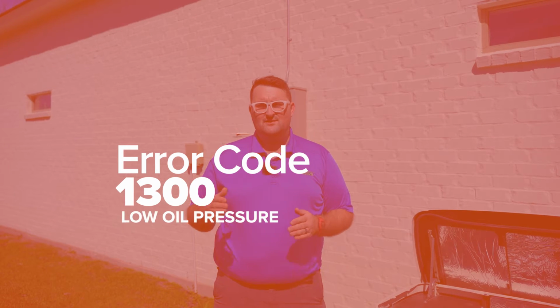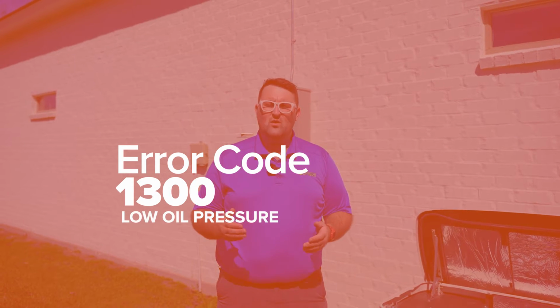The error code we're going to talk about today is the 1300 error code. That means low oil pressure. Your generator has an oil pressure sensor that senses how much oil pressure you have at any point, making sure you have enough oil pressure to run the engine safely and soundly. When the error code occurs, that means somewhere the oil pressure is low.